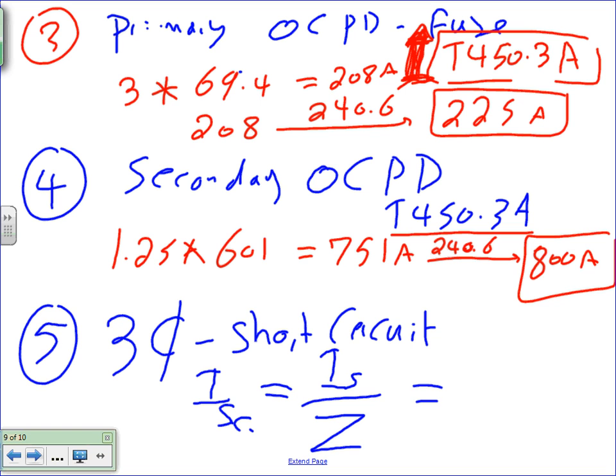Can we go back to the table, 450.3(A) or 3(B)? Okay, (A), there's two tables. Yeah, I see fuse rating, yep. You use (A) if either the primary or the secondary is higher than 600 volts, right? In my case, I have 4160, so I have to go to (A). Okay? And I use 3 because I'm using a fuse. Right? I'm asking for a fuse. On the secondary side, I think it doesn't matter, does it? In that table, I can't remember. Does it matter if it's a fuse on the secondary side or a circuit breaker?